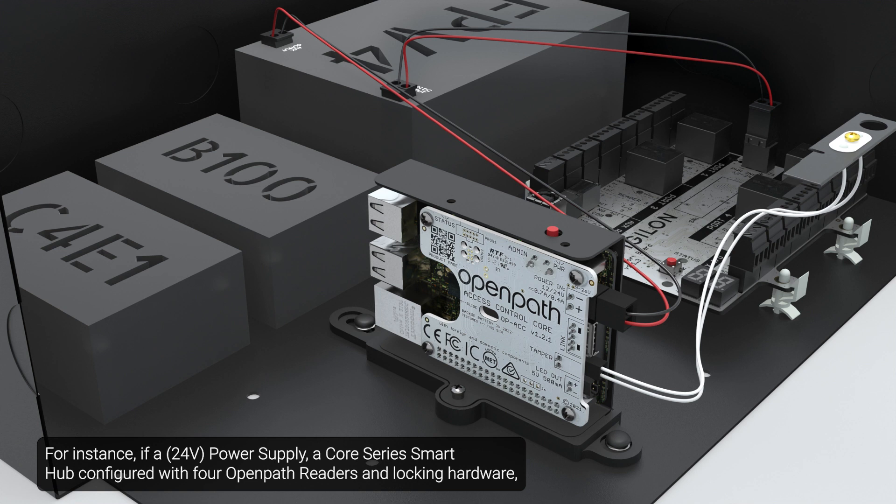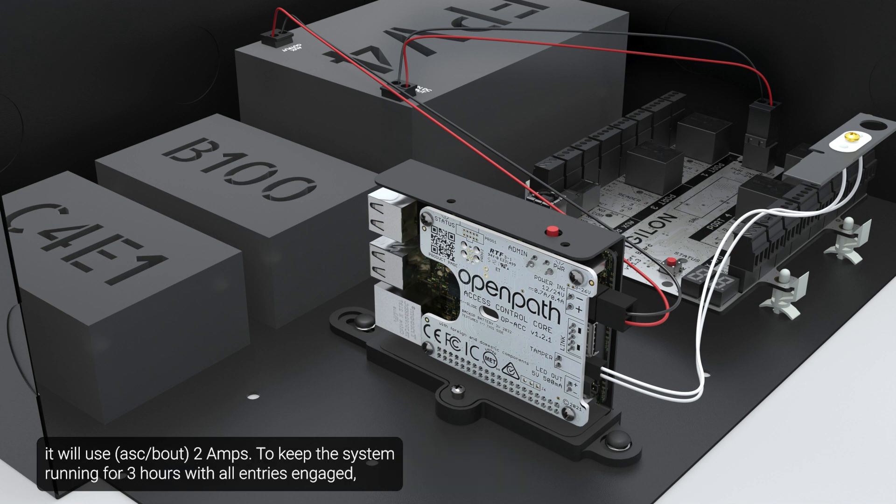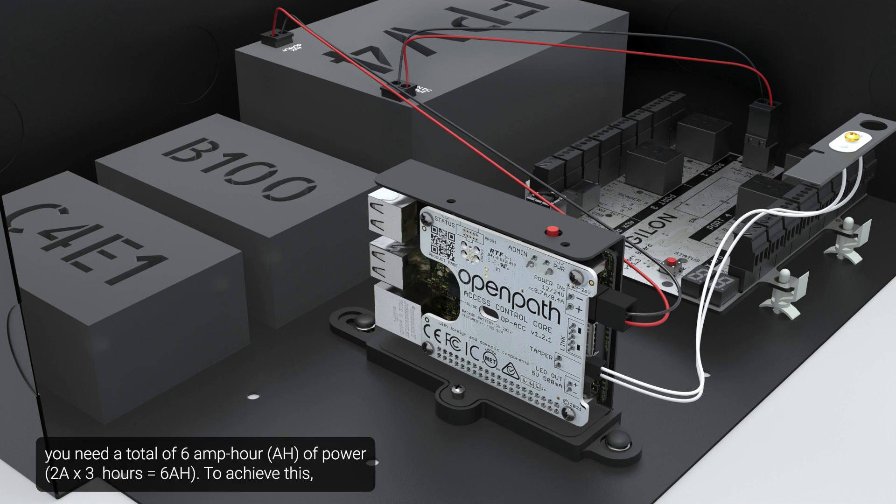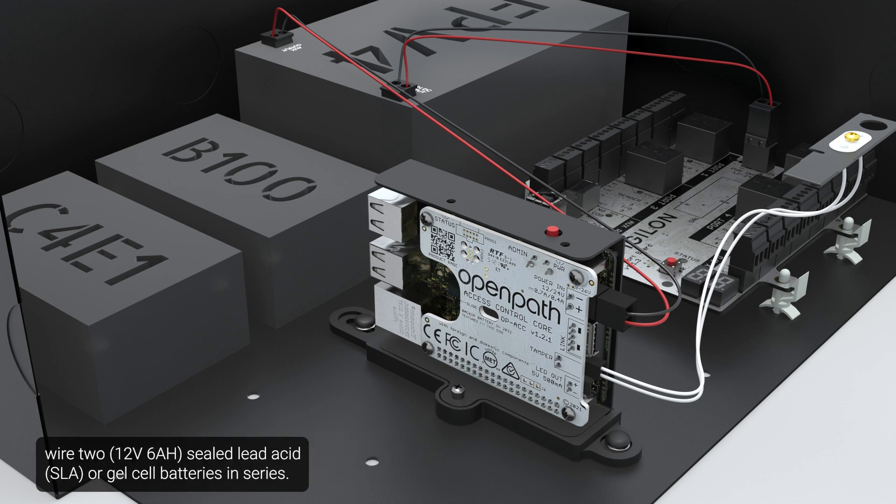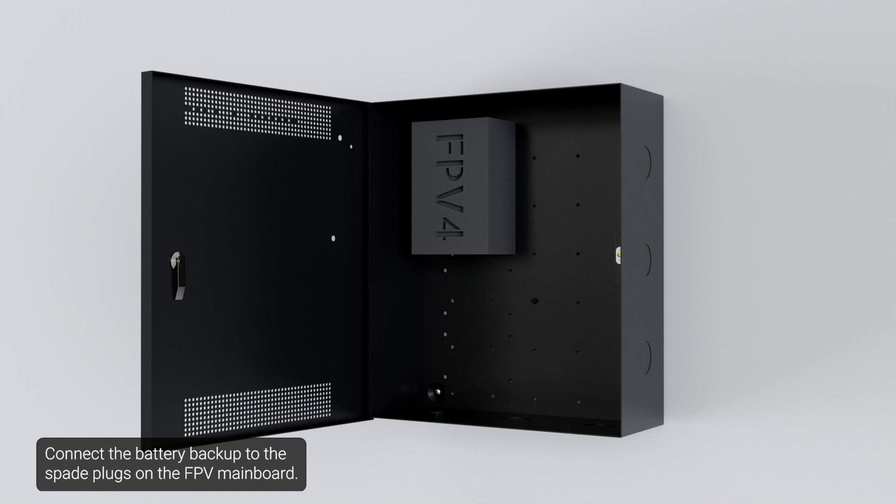For instance, if a power supply, a core series smart hub configured with 4 open path readers and locking hardware, it will use 2 amps. To keep the system running for 3 hours with all entries engaged, you need a total of 6 amp hour of power. To achieve this, wire two sealed lead acid or gel cell batteries in series. Connect the battery backup to the spade plugs on the FPV mainboard.